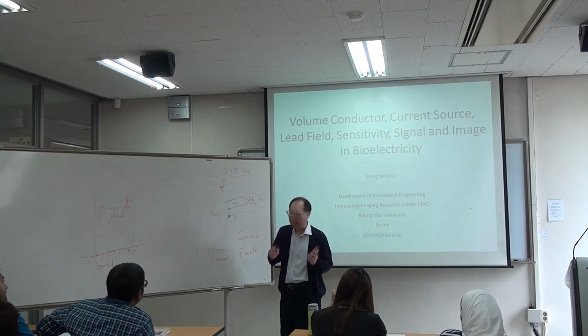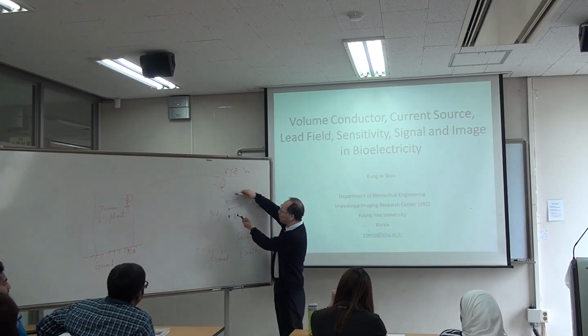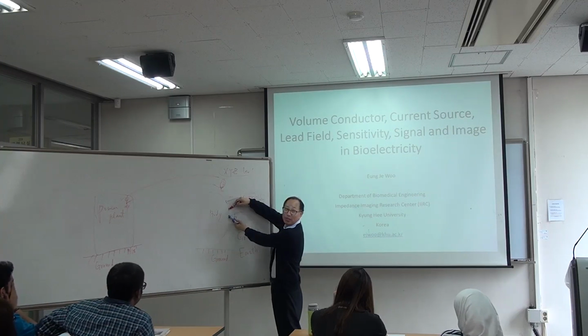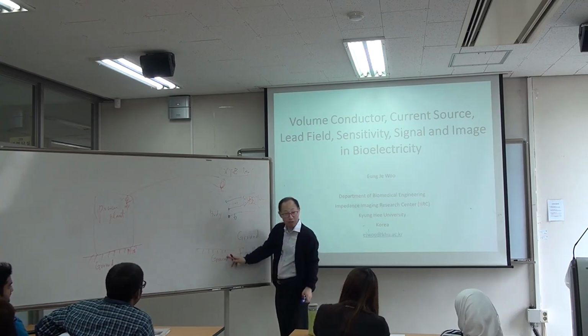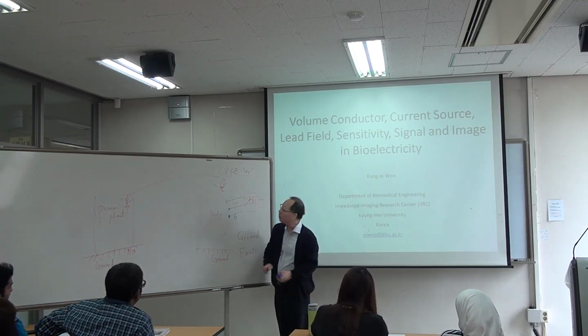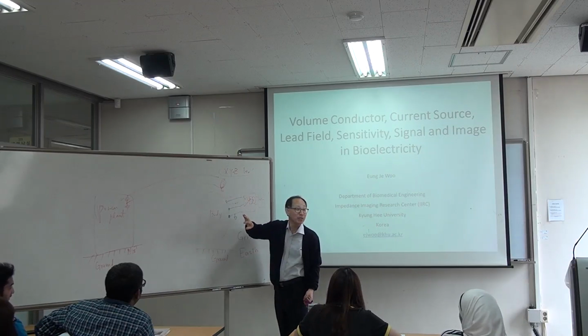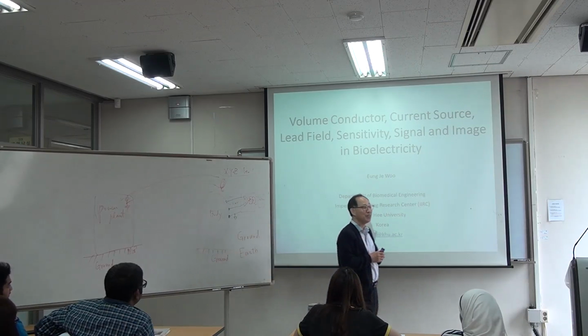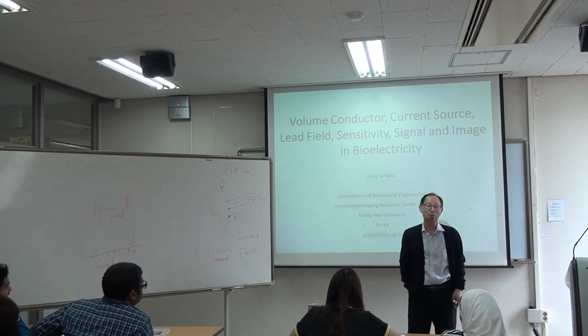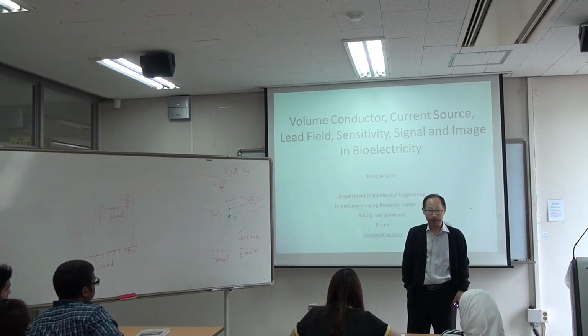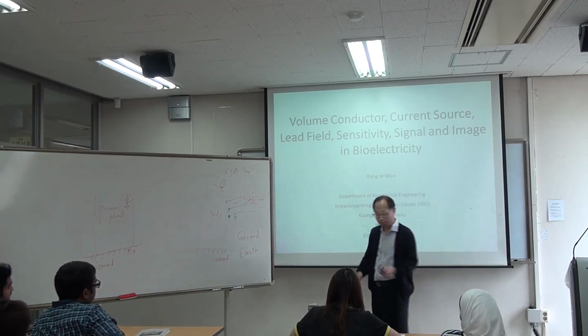So what I'm saying is, this point is 1 millivolt with respect to this point. This point is 0.9 millivolt with respect to this point. And this point and ground are not connected. Then what's the voltage difference between these 2 points? 0.1 millivolt. Is there any problem with that? No. There is no problem with that. This is perfectly fine.